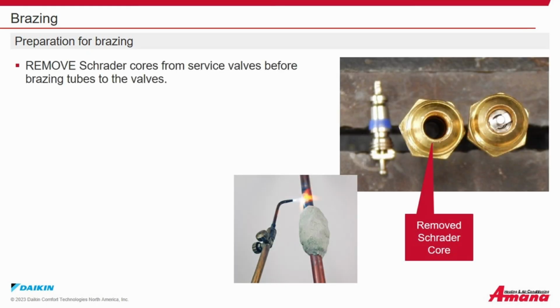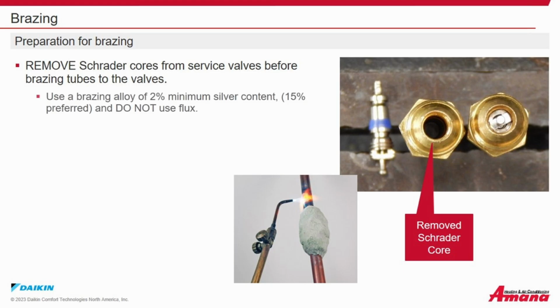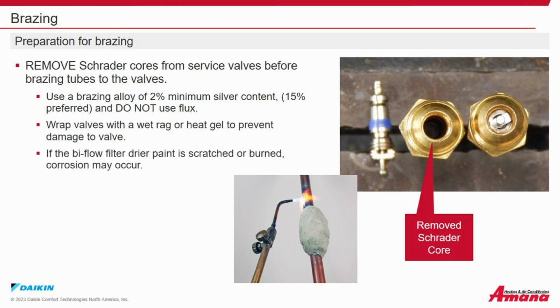Brazing. Preparation for brazing. Remove the Schrader cores from the service valves before brazing tubes to the valves. Use a brazing alloy of 2% minimum silver content, 15% is preferred, and do not use flux. Wrap valves in a wet rag or heat gel to prevent damage to the valve. If the biflow filter dryer paint is scratched or burned, corrosion may occur.